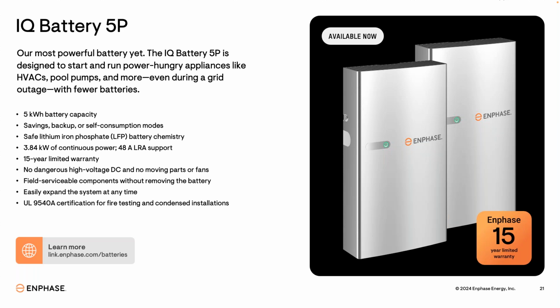It has a 15-year limited warranty, and 48 amps of LRA support. LRA is locked rotor amps, a specification you'll see on any motor-driven appliance like air conditioning and pumps. It's a big challenge for backup power systems, since LRA can basically cause a collapse of a battery backup system that can't handle that high level of current. Locked rotor amps really just applies for a split second, or maybe a little longer, when a motor-driven appliance first starts up.